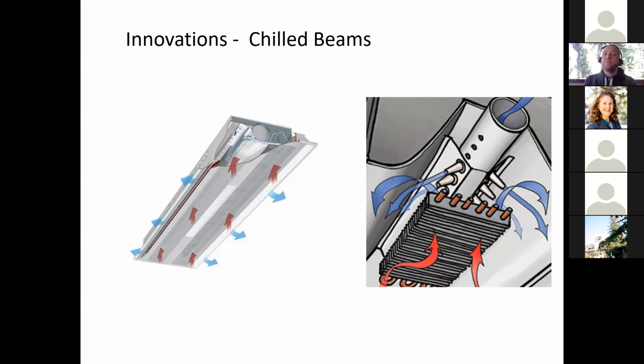And so it's a really effective way to use your ventilation air to actually mix a whole bunch more air in the space. So rather than having a normal diffuser, Gail showed a bunch of diffuser styles on Monday, instead of having a normal big diffuser that's designed to mix a whole bunch of air in the space, this is using just a little bit of air and using natural laws of physics to suck air from the room over these coils. So we use chilled beams all the time. We have two projects right now up at LBNL, up at the lab, that use chilled beams for labs. So they're a really effective system.